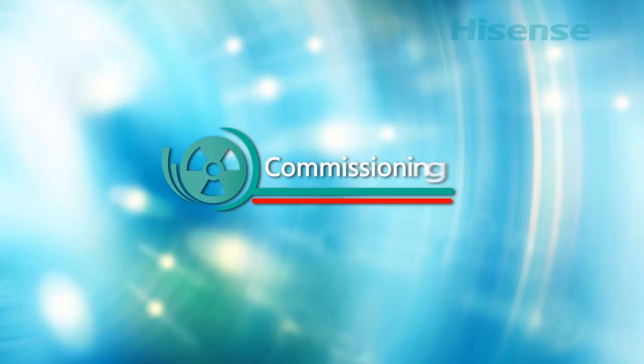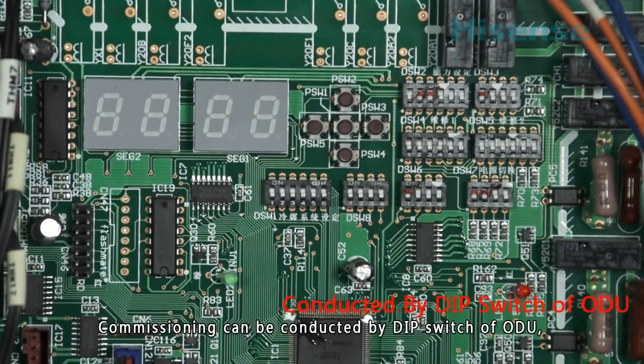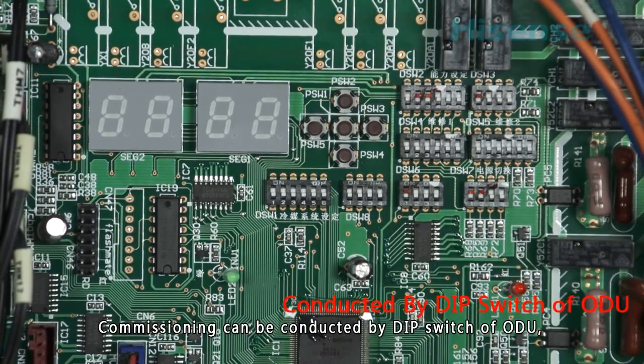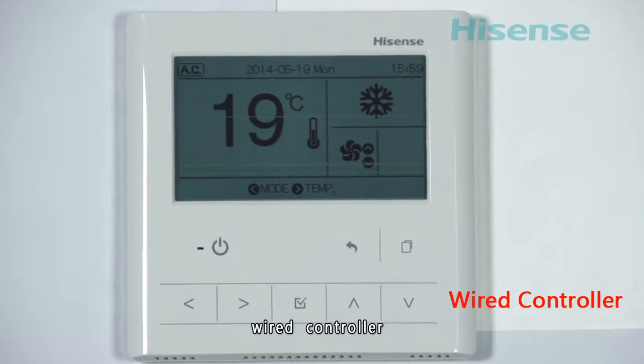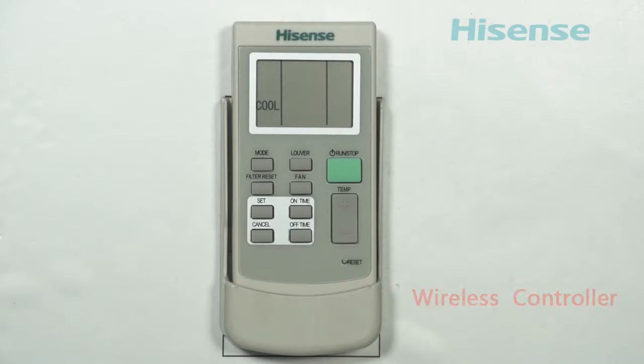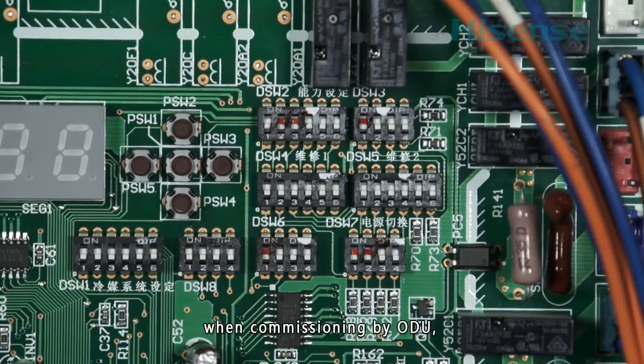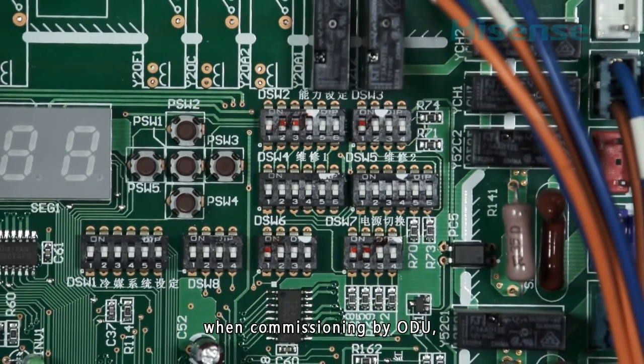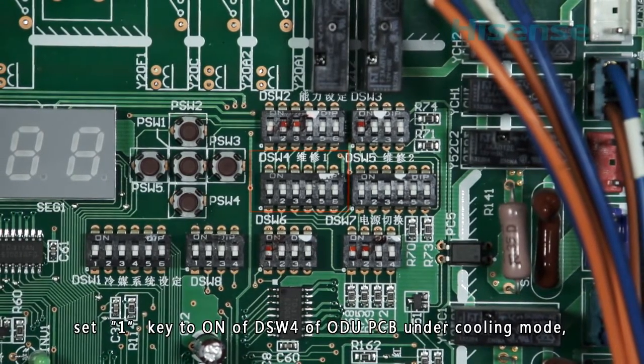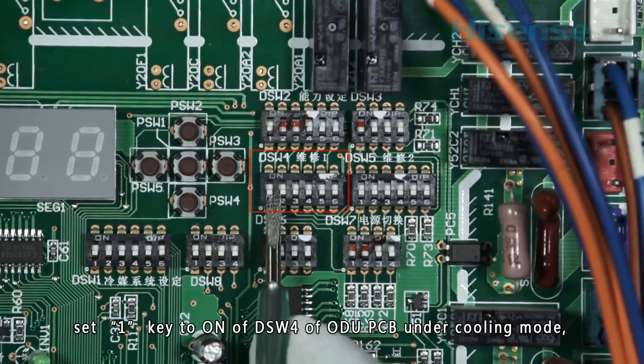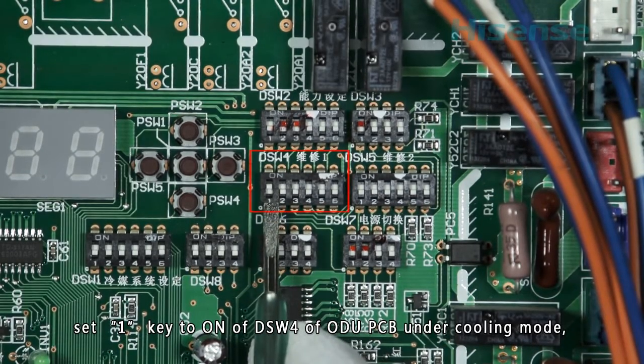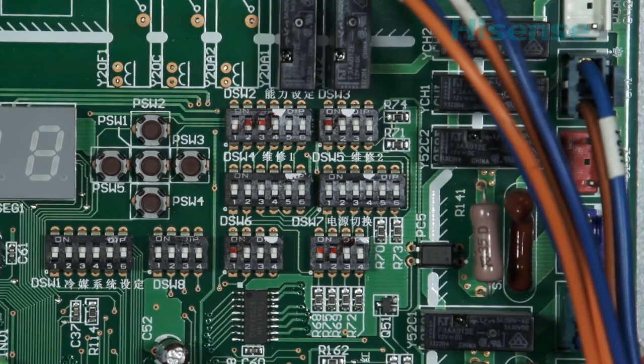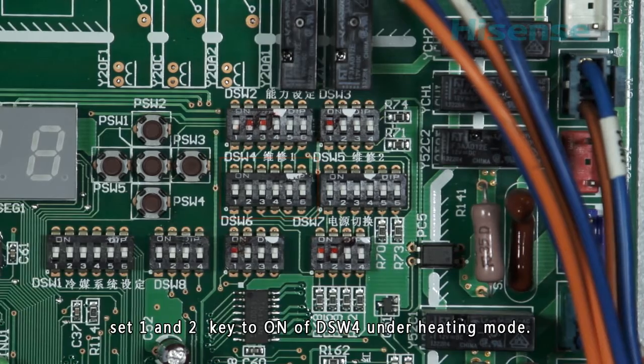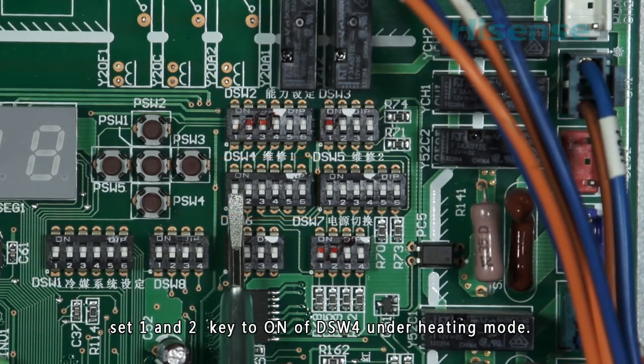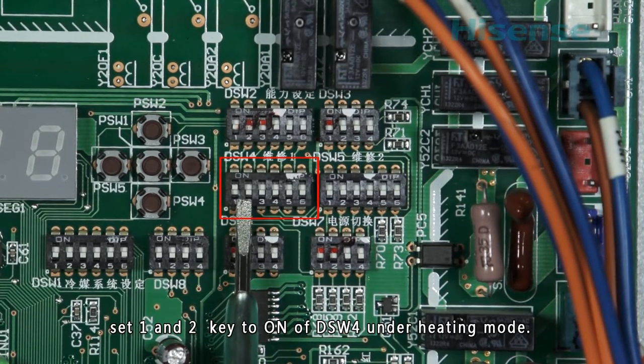Commissioning. Commissioning can be conducted by dip switch of outdoor unit, wired controller, wireless controller. When commissioning by outdoor unit, set one key to on of DSW4 of outdoor unit PCB under cooling mode. Set 1 and 2 key to on of DSW4 under heating mode.